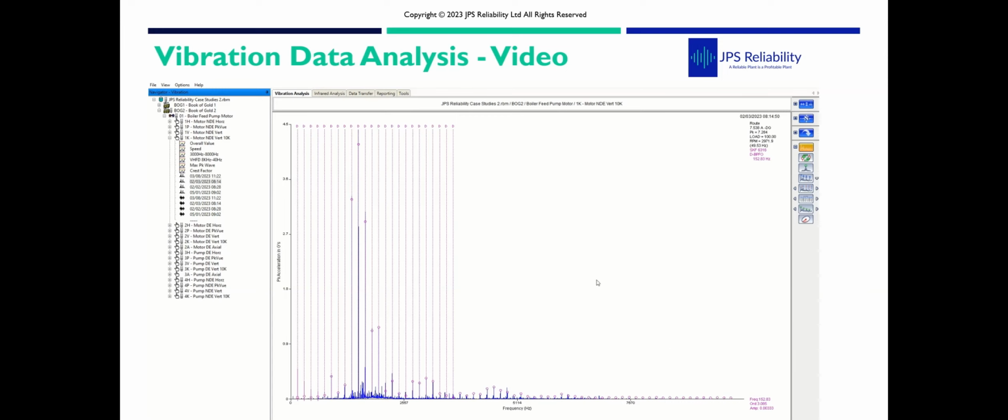But what's different about this, which shows you it's EDM, is you usually get this high amount of activity, sometimes around the drive frequency, and it's sidebanded by outer race, whereas a normal outer race defect frequency, you usually get a higher one order BPFO, 2, and it sort of comes down like it's ringing. This is the bearing basically screaming because of the drive.